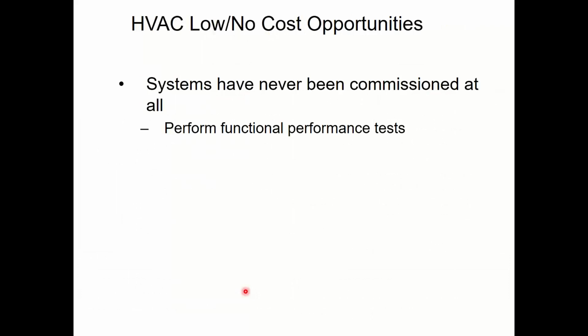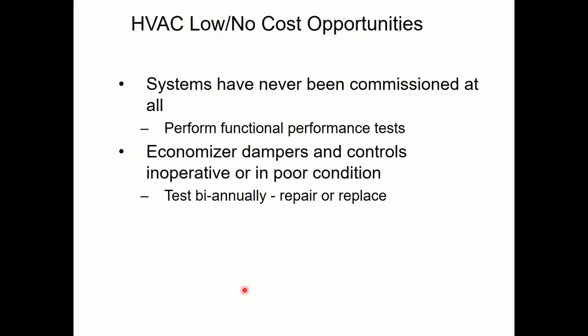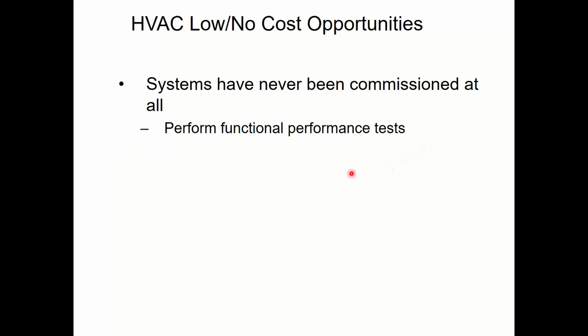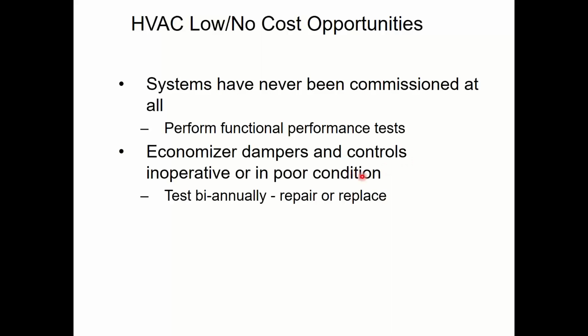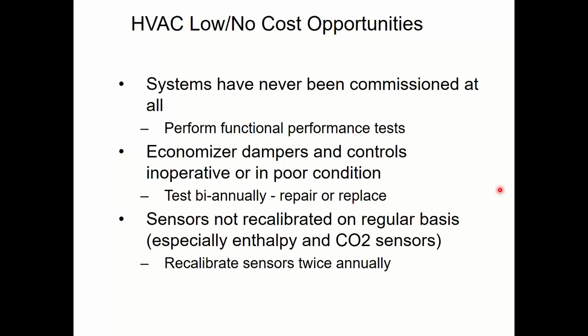All right, so these low cost, no cost things that we're talking about, testing everything, that's step one. Make sure things are working the way they're supposed to be working. If they're not, fix them to make them work the way they're supposed to work. Testing the economizers has to be part of the discussion. When someone's compressor breaks or when their gas heat breaks, it gets noticed pretty quickly on the next really hot or really cold day. If somebody's economizer breaks, it doesn't get noticed because the compressor takes over and solves the problem for you automatically, and hence you don't know your economizer is broke, but you're wasting hundreds, if not thousands of dollars in that process. So we'll talk about that today too.